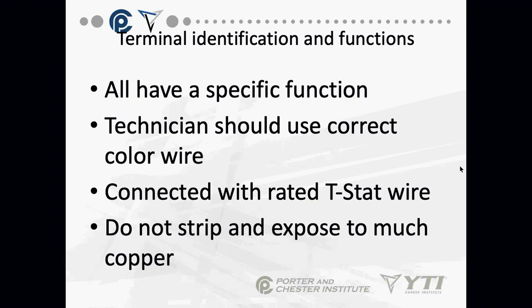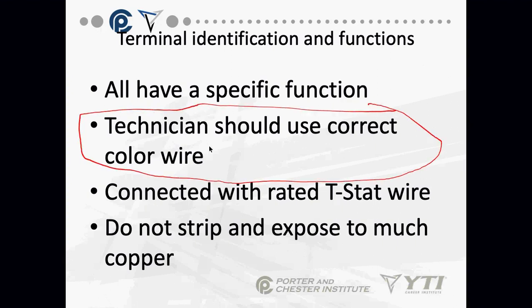Now, I'm going to tell you right now, don't count on wire colors. All of your thermostats have a Y terminal, and there should be a yellow wire on there, but there's a lot of thermostats now that are connected with Cat5 wire. Try to find a plain yellow wire in Cat5 cabling. That's computer network cable. You're not going to find wire sometimes with the correct color, so just be very aware. You have to figure out what color wire they used and be able to look at the thermostat side and the equipment side and make sure the wire color matches.